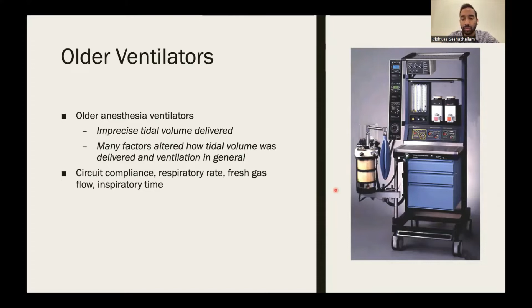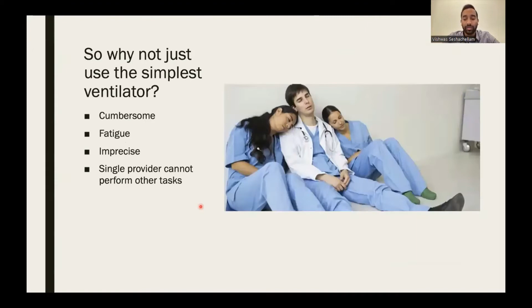Because of this, we started to use ventilators. Older anesthesia ventilators looked like this. I've seen maybe 1 or 2 in my life. The con to using this type of ventilator is that the desired tidal volume will not always be delivered. Think about your small neonates, small infants that have to undergo ventilation. If a set tidal volume was delivered here, the circuit compliance, respiratory rate, fresh gas flow, inspiratory time, several other factors, the bellows, the compliance of the ambu bag, they all factor into how much volume is actually being delivered to a patient. So if you need to deliver a tidal volume of 12 and you dial this in, this tidal volume may change to 20, 25. You don't really know what tidal volume is being delivered when. So it's a major drawback for these ventilators. However, it was better than hand ventilation.